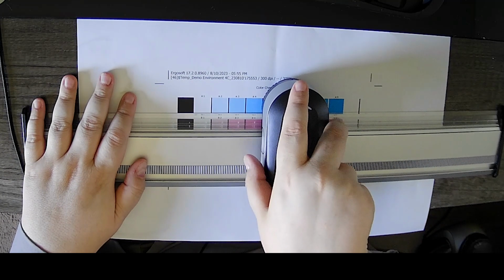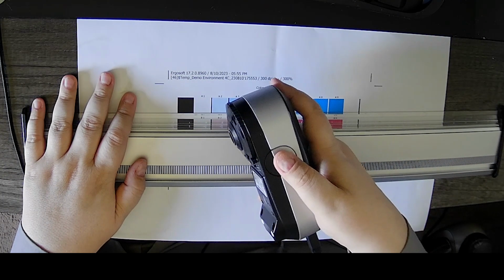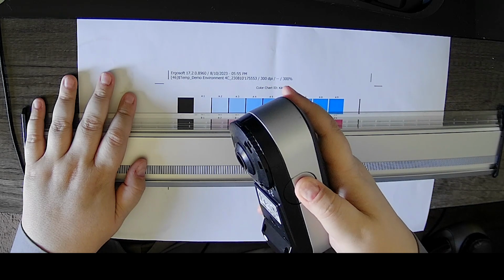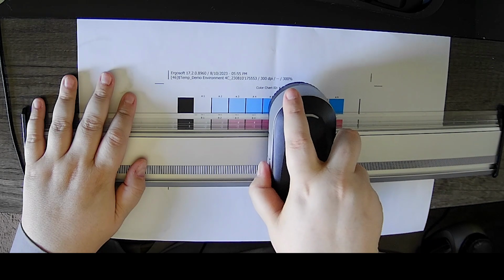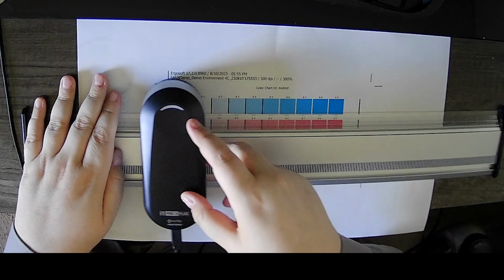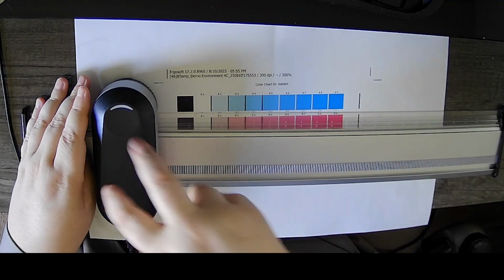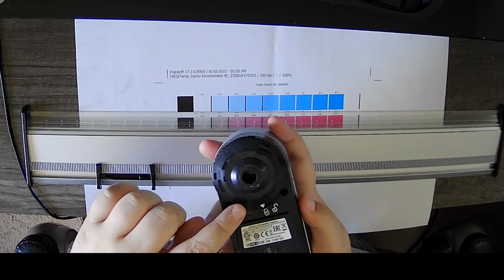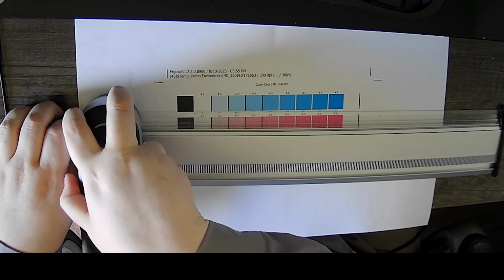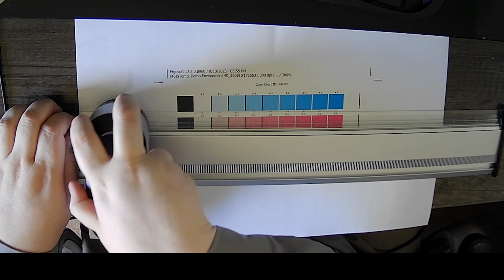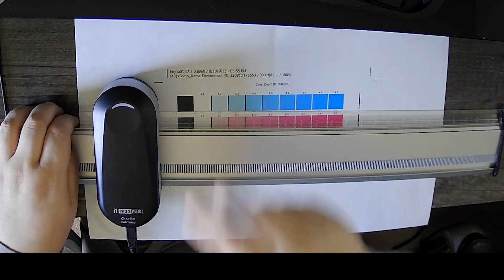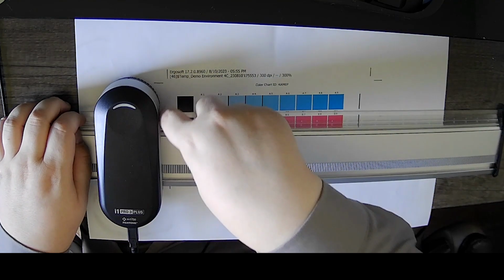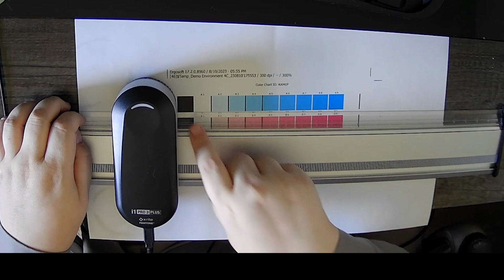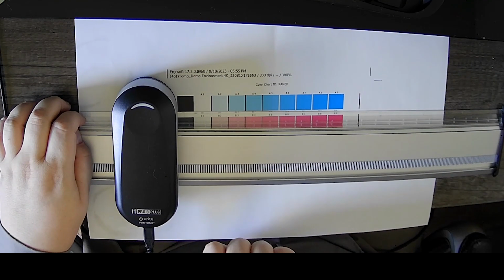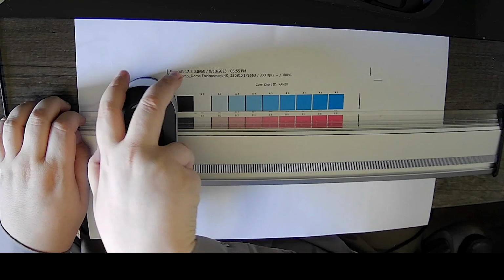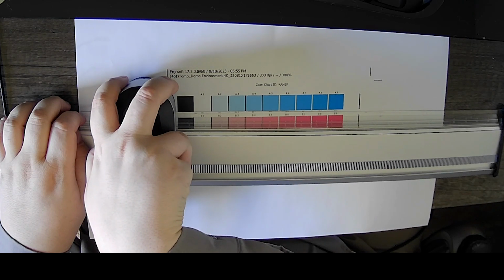Then we push the button on the side here, right there, and you hold it. You'll hear a beep. So you put it to the side, and you want to start it. Once again, I'll show you this. This is the aperture, in the middle of the device. What we need to do is put the middle of the device to the left of the first patch. I usually just put it so I can see the patch there. We're going to push the button and hold it until we hear the beep.